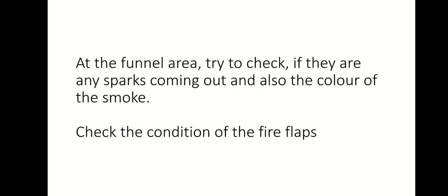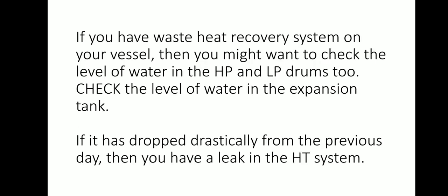We will also check the condition of the fire flaps. Then we will enter the boiler platform. If your vessel has a waste heat recovery system, you have to check the water level in the high pressure and low pressure drum.